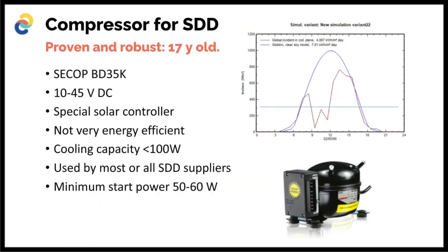This compressor is quite old. It's called SECOP BD35K. It was originally developed for trucks and mobile appliances, but since then it was adapted with a special solar controller, so we can have this very smooth start. It's not very energy efficient, which is a drawback, and the cooling capacity is also quite limited, to around 100 watts.